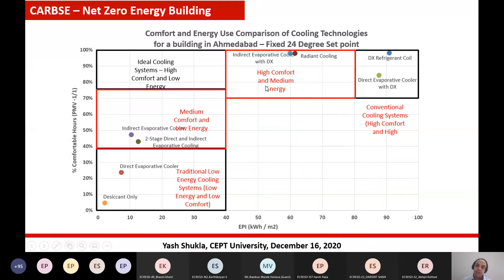All right. So we chose to go with high comfort and medium energy system, which is a radiant cooling system. And this is what we installed in our building. What you see on the left side is a typical radiant panel. So what is a radiant panel? It has a water pipe inside a panel sandwiched, so you can pass the cold water inside that panel and achieve comfort. So we actually make the whole envelope or the surfaces colder, and that makes the heat loss easier for the occupants and makes them feel a little bit more comfortable.